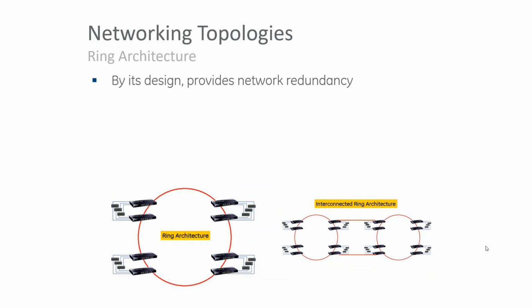One popular option is the ring architecture. In a ring, all the devices are connected in a loop rather than point to point like in the star architecture. It provides redundancy: if there's a break in the ring one way, data can be rerouted the other way, or if you lose a switch, data can be rerouted around the other side. So it provides redundancy without the additional cabling cost of a mesh or redundant star architecture.